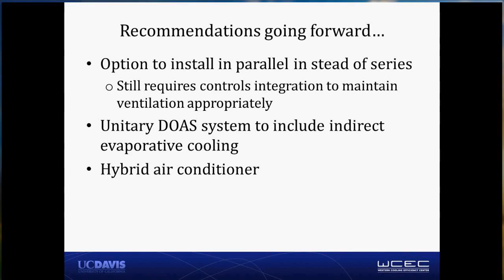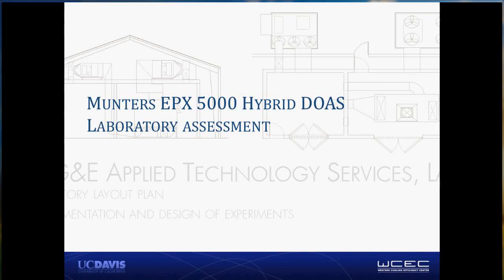I mentioned the opportunity to install these things in parallel instead of series. We think that they can, should, and actually are being integrated into unitary DOAS equipment so that they don't have to take the same form factor you see, but could exist as a heat exchanger within a larger unitary air handler that commercial buildings are more familiar with and which are readily integrated into existing building management systems. And also to note that the Western Cooling Challenge has always held in mind the need for integrated and packaged hybrid air conditioners that can replace rooftop units one for one, have indirect evaporative cooling plus vapor compression integral.